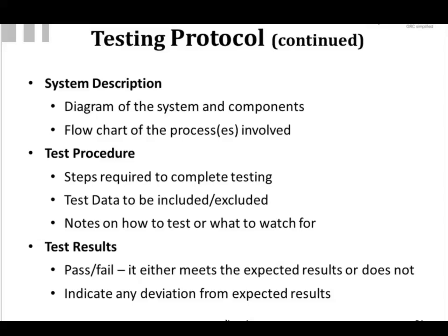Your test procedure itself, the steps of the test scripts, these steps are required to complete your testing. Test data should be identified as what data you're including and what data you're not including. So you want to highlight which set of test data you're going to use for this. You want to make sure, at least in PQ, that that test data is a simulated version of your real data. And then you want to have notes on how you're going to test or what you're going to watch for, indicating how you're going to proceed.